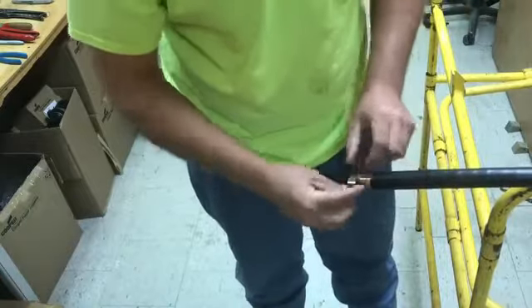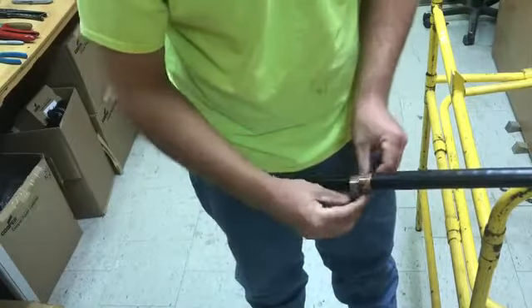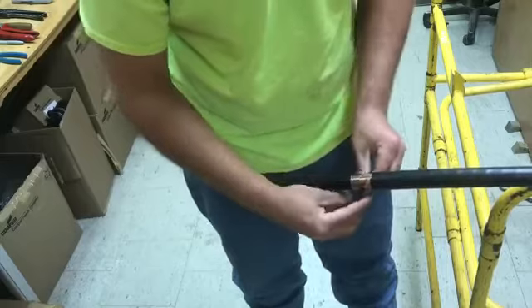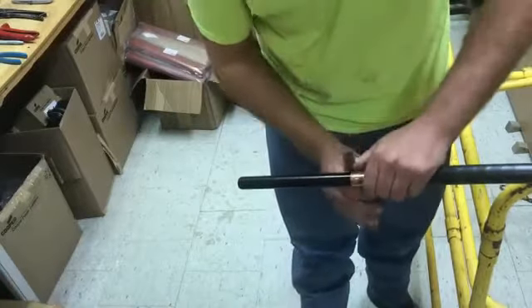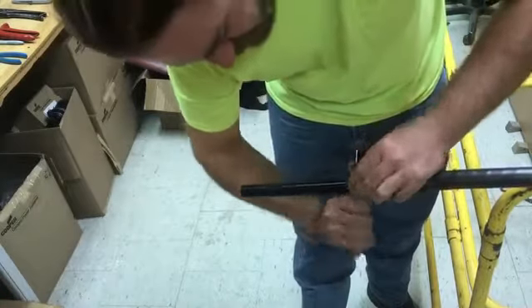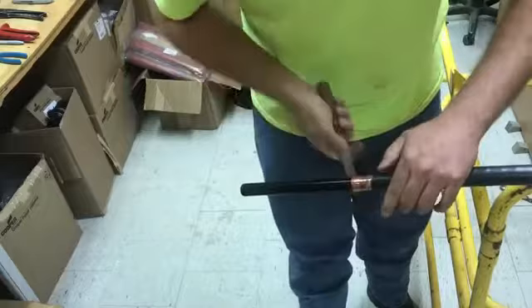I will now remove the constant force spring. Because I put the copper tape on top of the copper tape shield, I can remove the constant force spring without unraveling the copper tape shield. I'll then take my shoe knife with the blade pointed towards the copper tape shield and flatten out any sharp edges.